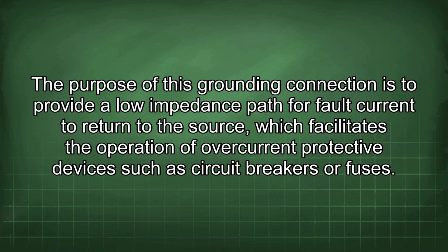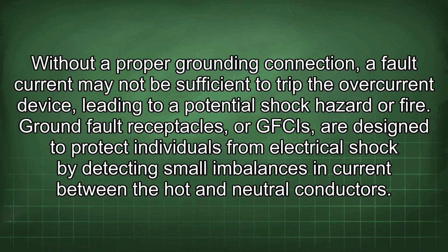The purpose of this grounding connection is to provide a low impedance path for fault current to return to the source, which facilitates the operation of overcurrent protective devices such as circuit breakers or fuses. Without a proper grounding connection, a fault current may not be sufficient to trip the overcurrent device, leading to a potential shock hazard or fire.